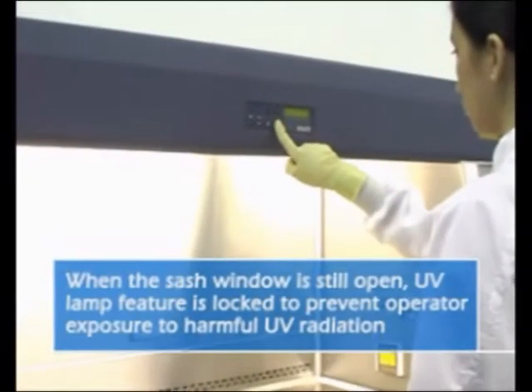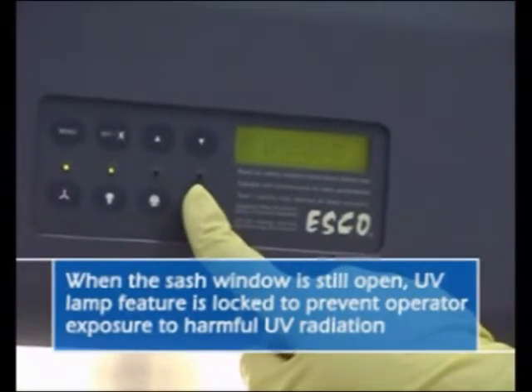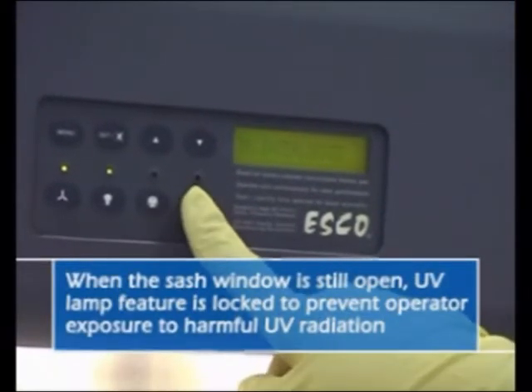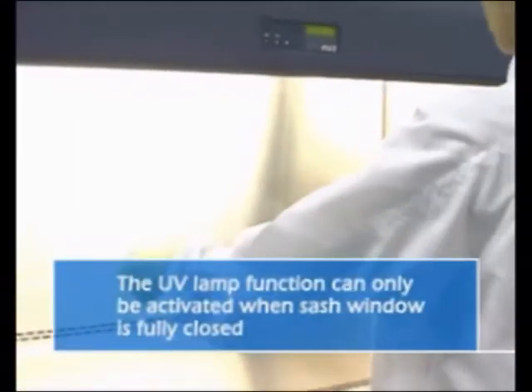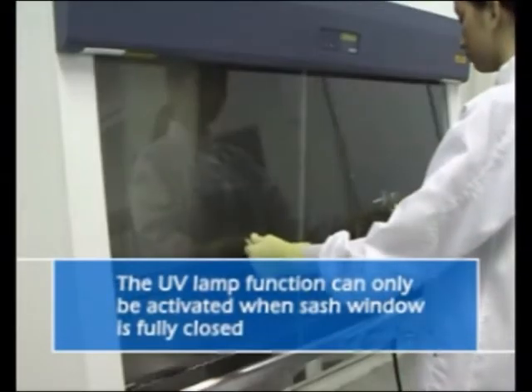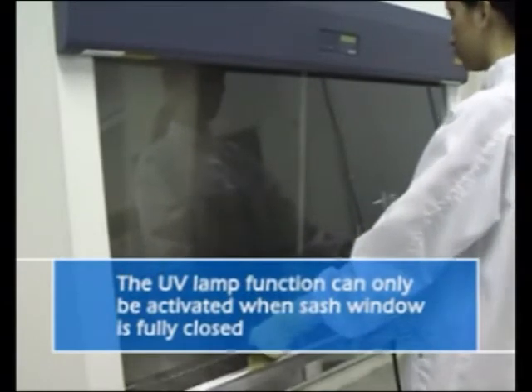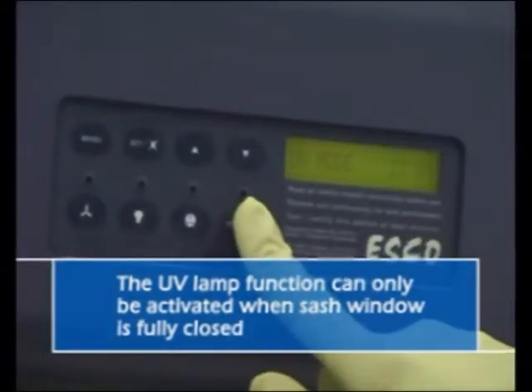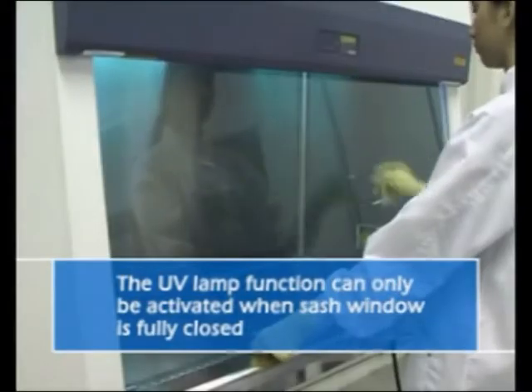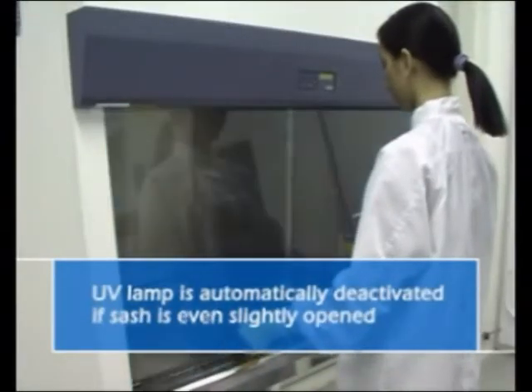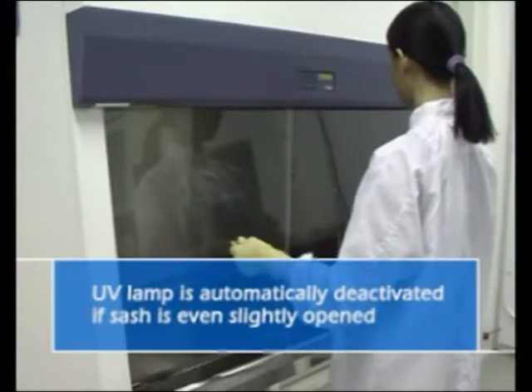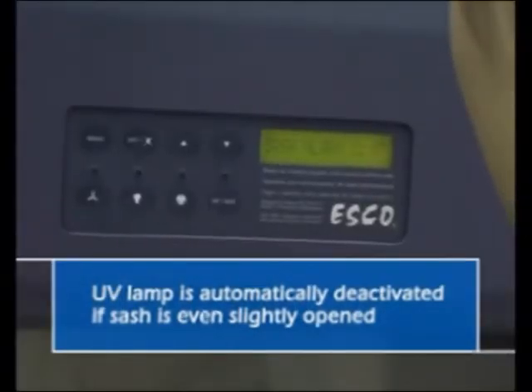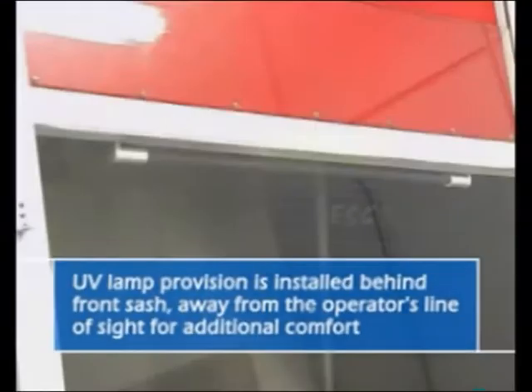The ultraviolet germicidal lamp on the cabinet control system is interlocked with the sash window position for additional safety. This means that the UV lamp may not be activated unless the front protective sliding sash is fully closed. The UV lamp is automatically deactivated once the sash is even slightly moved from its fully closed position. The UV lamp is installed out of the operator's line of sight, ensuring protection to the operator from direct UV radiation.